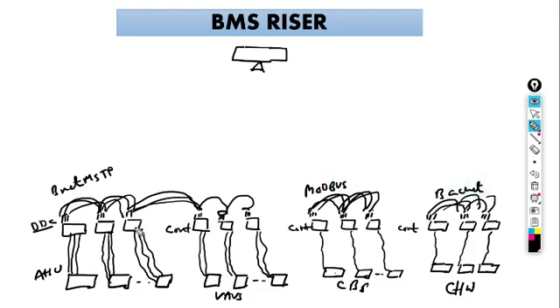It's not necessary that they all use BACnet or all use Modbus. For electrical systems like VFDs, it's better to use the Modbus system. In mechanical systems like AHUs and VAVs and chilled water systems, it's better to use BACnet MS over TP protocol, master slave token passing.